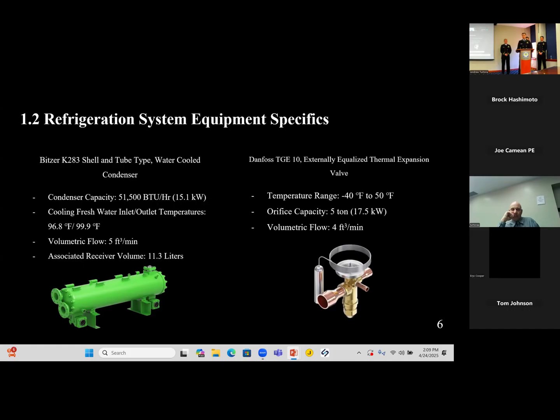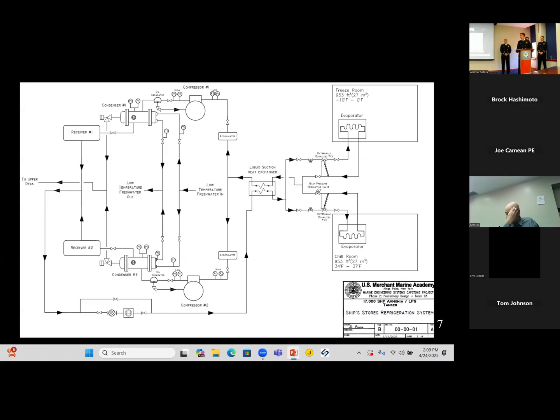Lastly, in our system, we used Danfoss externally equalized TXV valves because of the large temperature range from -40 to 50 degrees Fahrenheit, an orifice capacity to meet system requirements of 5 tons, and an adequate volumetric flow rate of 4 cubic feet per minute. Additionally, these externally equalized control valves were used because of the large pressure drops experienced within the evaporators, which are greater than 2 psi. So, next up, we're going to view the overall system schematic drawing of the refrigeration system.